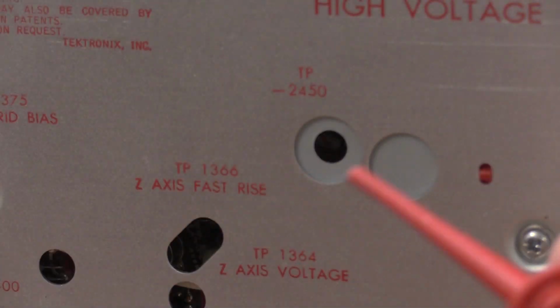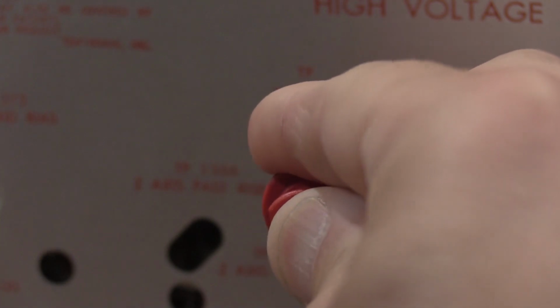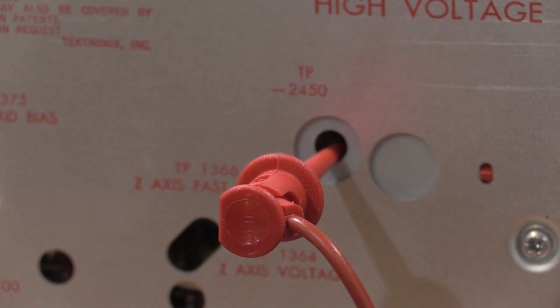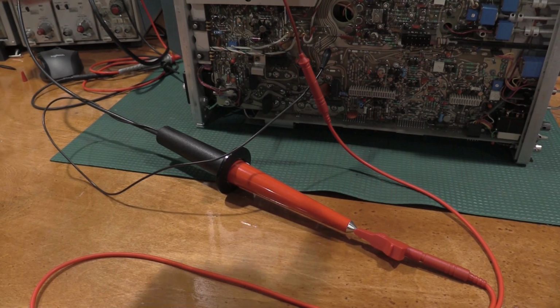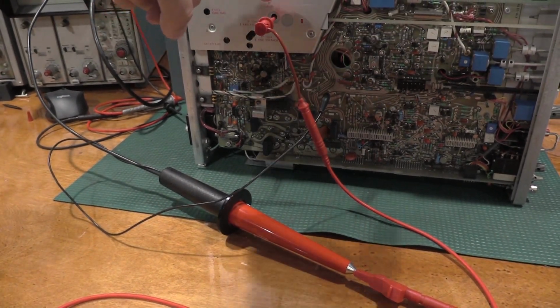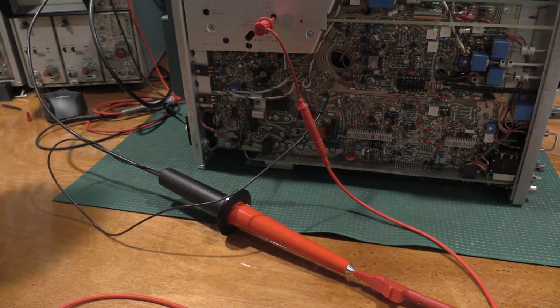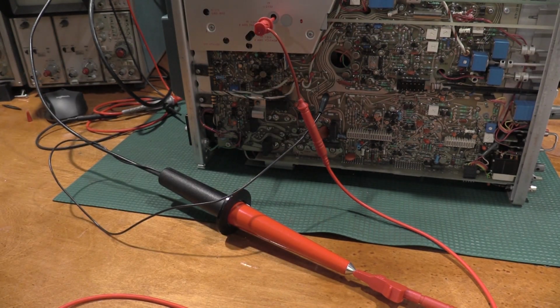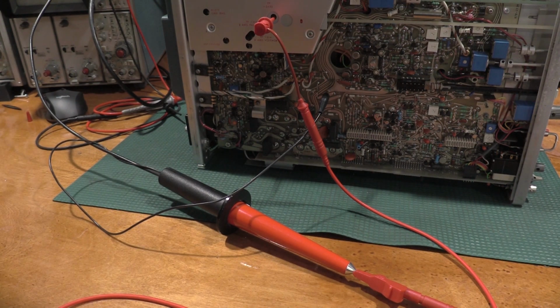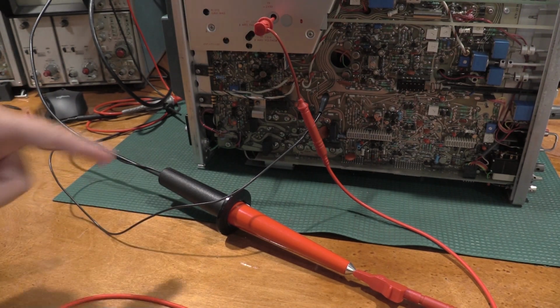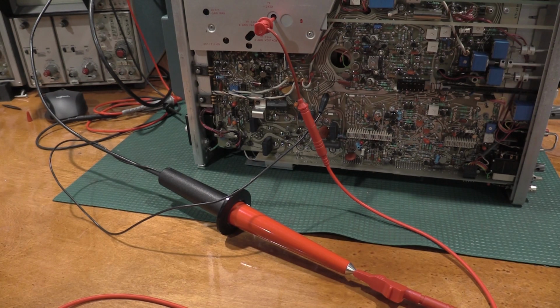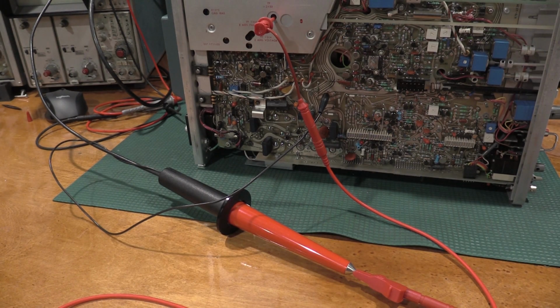Okay, we're hooking up the probe to the negative 2450 volt test point. Now I have the scope turned off. Yep, I'm on there. So I need to get my high voltage probe. Okay, we just have the high voltage brought out from right here down into this clip on the high voltage probe, hooked up to the meter. We're on the 200 volt range on the meter, which we know from previous testing is the most accurate for the high voltage probe. Hooked up to ground. Double checking we are hooked up to ground since we're playing with spicy voltages. We are. Turning the scope on gives us a meter reading.